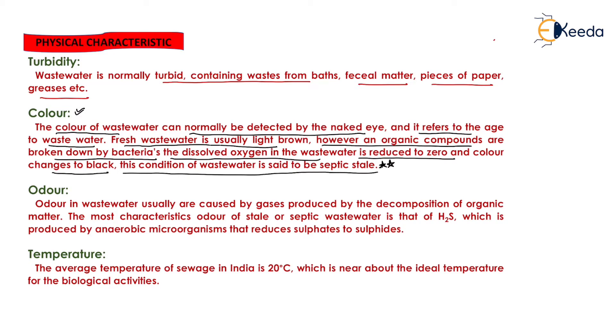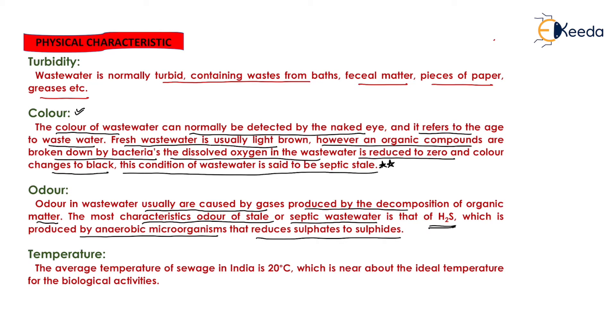Odor in wastewater is usually caused by gases produced by the decomposition of organic matter by microorganisms. The most characteristic odor of stale or septic wastewater is that of H2S, which has a pungent smell. H2S is produced by anaerobic microorganisms that reduce sulfates to sulfides. When anaerobic microorganisms decompose organic matter reducing sulfates to sulfides, H2S is liberated, giving wastewater its characteristic pungent odor.